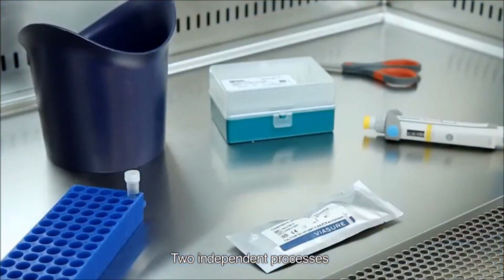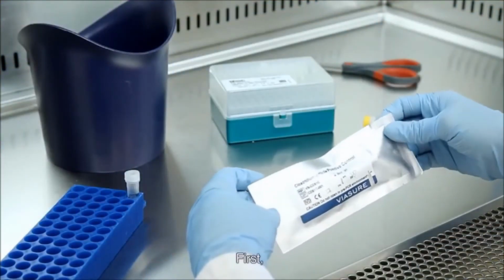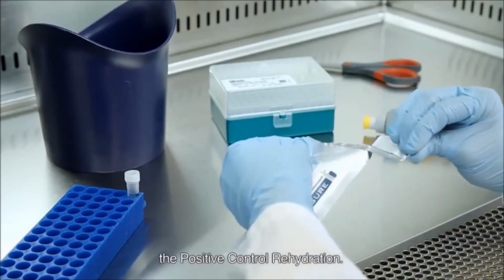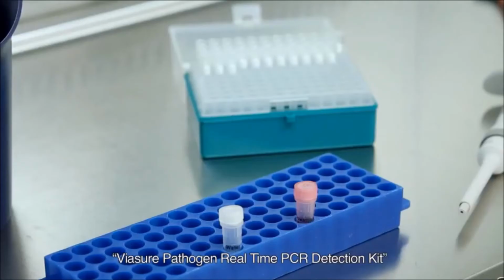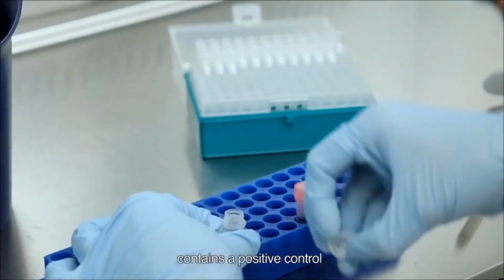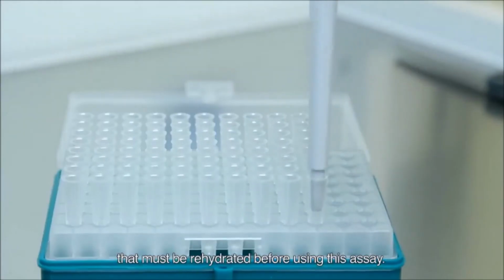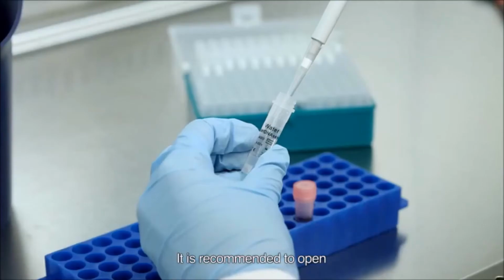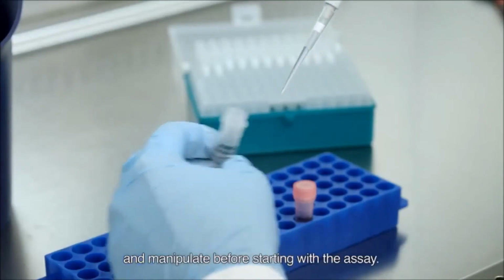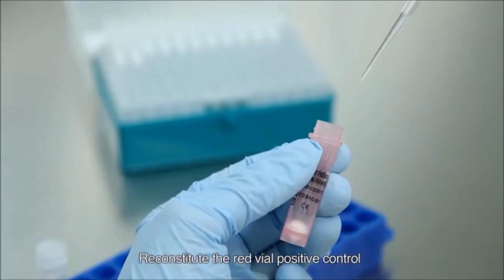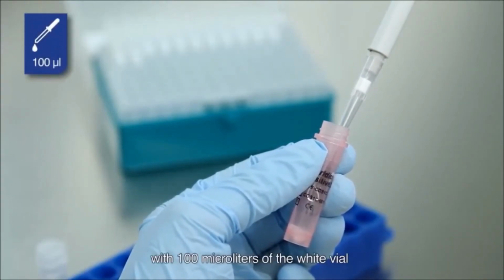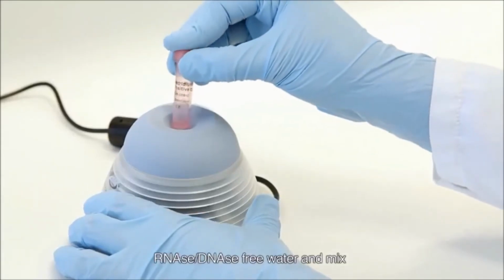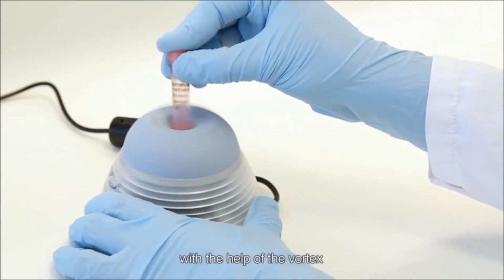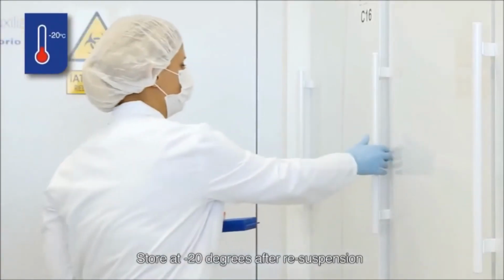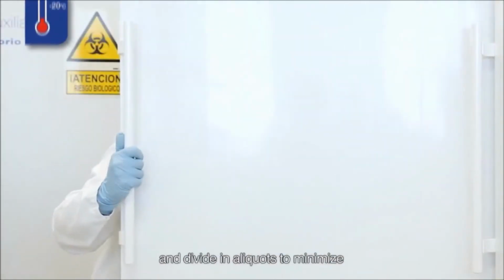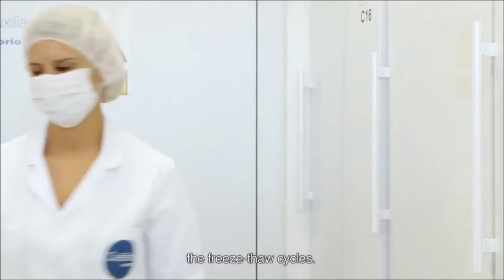Two independent processes are made in the third area. First, the positive control rehydration. The ViaSure Pathogen Real-Time PCR Detection Kit contains a positive control that must be rehydrated before using this assay. It is recommended to open and manipulate it before starting with the assay. Reconstitute the red vial positive control with 100 microliters of the white vial RNase, DNase free water and mix with the help of the vortex. Store at -20 degrees after resuspension and divide in aliquots to minimize the freeze-thaw cycles.